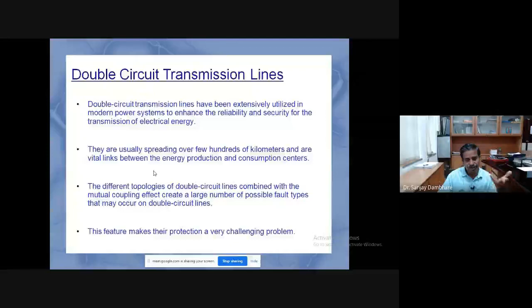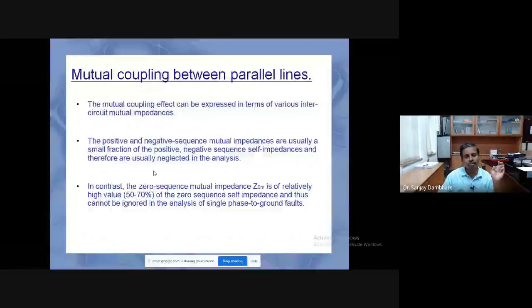As they are completely independent, those modal currents can be used for relaying purposes. So you can implement the differential protection scheme not on the phase current but on the modal current, and that scheme will be independent of the mutual coupling — that is the advantage.